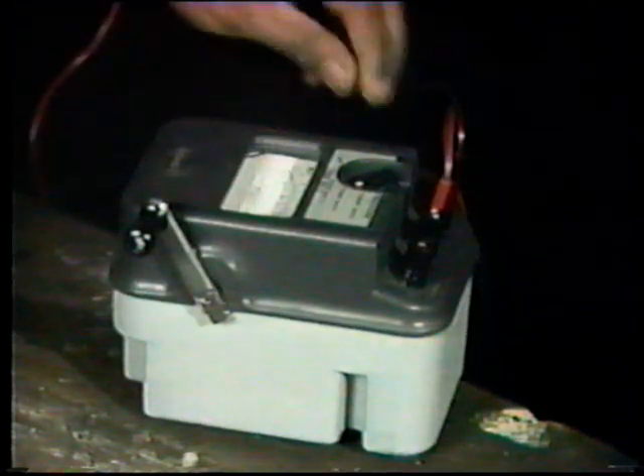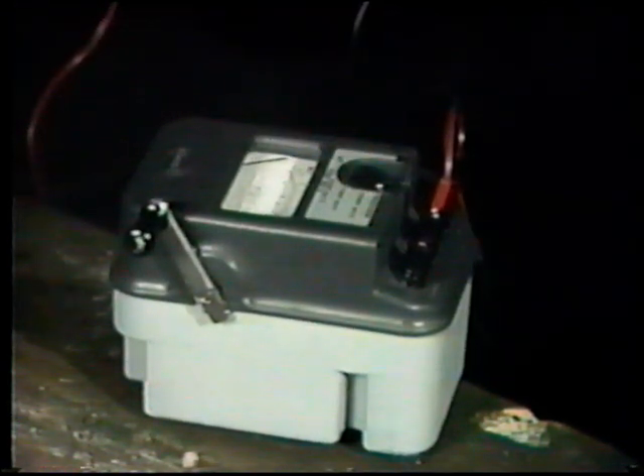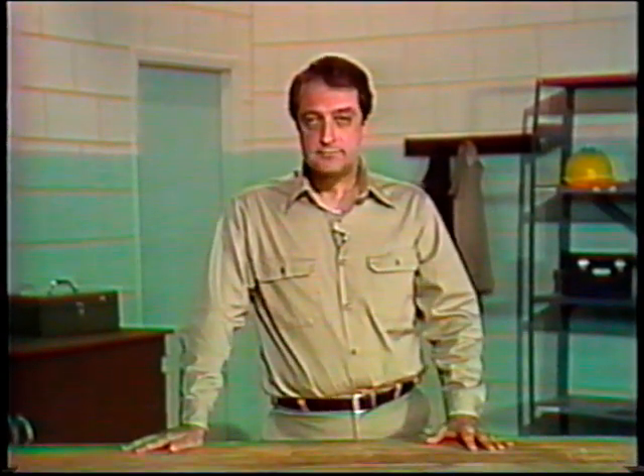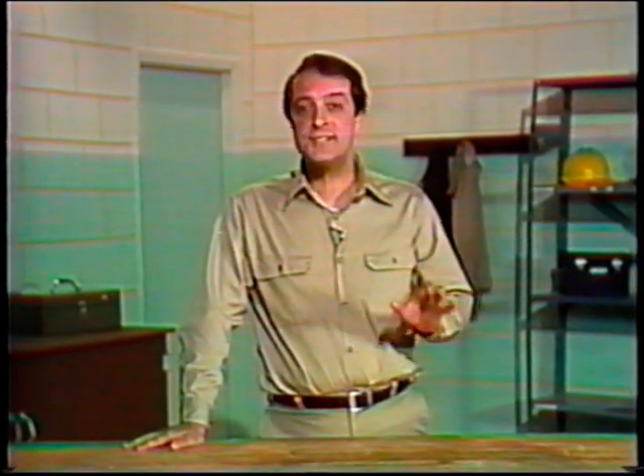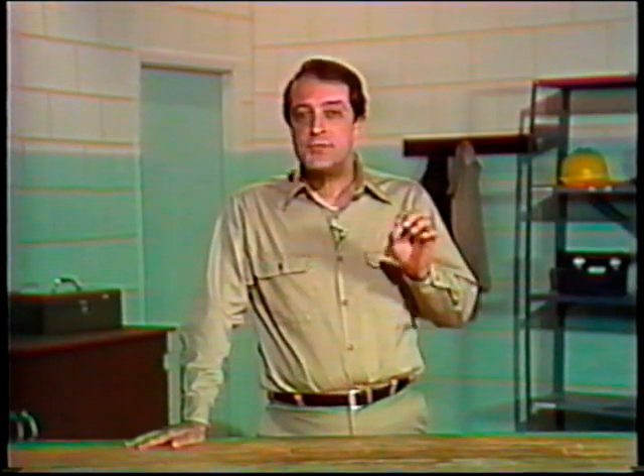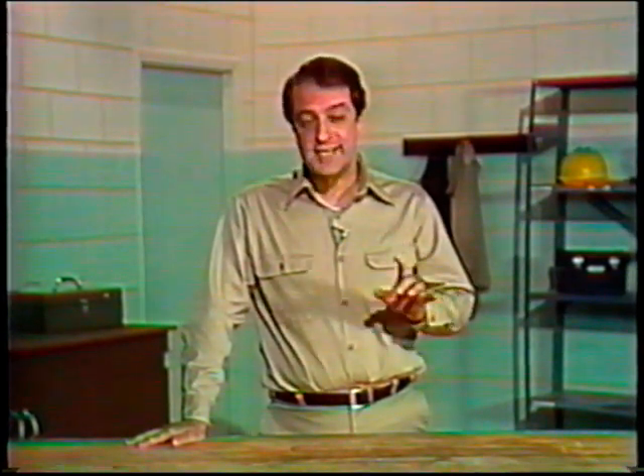The rotor receives a charge from the meg-ohm meter, so it must be discharged at the end of the test. In most plants, the readings from insulation tests are recorded and evaluated to see if a trend is developing. In this way, insulation deterioration over a period of time can be detected. As we've said, the insulation test can also be taken on the stator of a synchronous motor. The procedures for the stator are similar to those for the rotor. The main difference is that to test the stator, the motor leads are clipped together and the 3 phases are tested together.